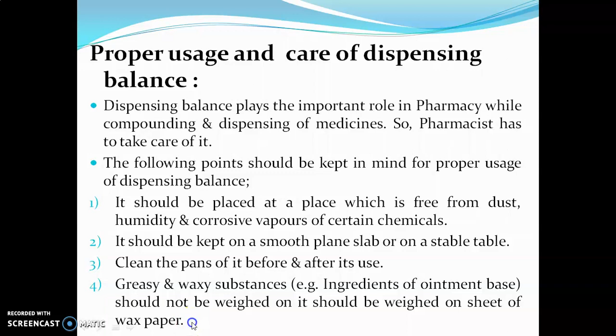Third, clean the pans before and after use. Fourth, greasy and waxy substances, for example ingredients of an ointment base, should not be weighed on it directly but should be weighed on a sheet of wax paper. Fifth, always use a spatula to transfer material from bulk packing to the pan. Sixth, the drawer of the balance is closed while weighing. Seventh, weights should be transferred with the forceps. Eighth, after using the balance, it should be cleaned with a soft cloth or brush. Ninth, when the balance is not in use, it should be cleaned and covered with the balance cover.